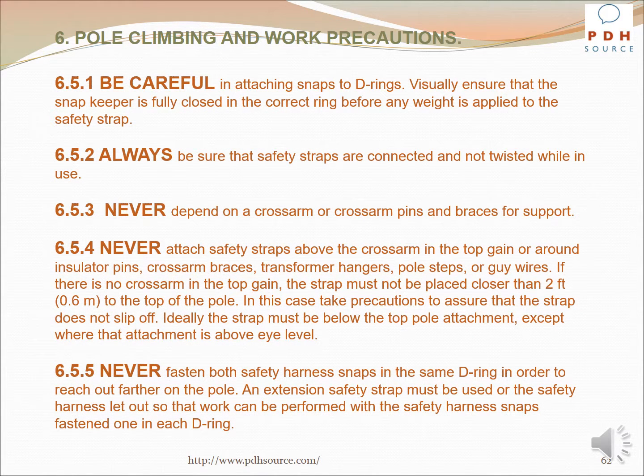Be careful in attaching snaps to D-rings. Visually ensure that the snap keeper is fully closed in the correct ring before any weight is applied to the safety strap. Always be sure that safety straps are connected and not twisted while in use. Never depend on a crossarm or crossarm pins and braces for support.